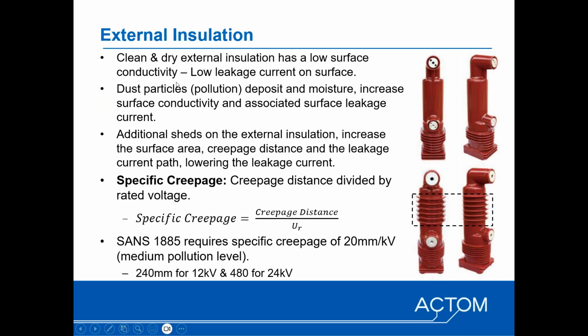In terms of the insulation itself, when it's clean and dry, you've got a very low surface conductivity. So the leakage current over the surface would be very, very low. But when dust particles and moisture get in contact with the surface, which then dissolve the dust and the salts inside the dust, then the conductivity of the surface increases, and the leakage current on the surface then increases.